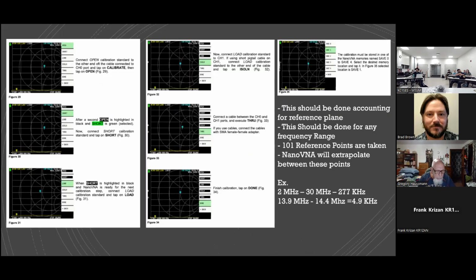Calibration. Again, this looks like a lot, but it's pretty straightforward. You open up the calibration window, and then you literally connect your open standard, and you tap open. You take your open off, you connect your short, you tap short. You take your short off, you connect your load, you tap load. Isolation is basically, you put the load on one and it tests the difference between the 2 ports.